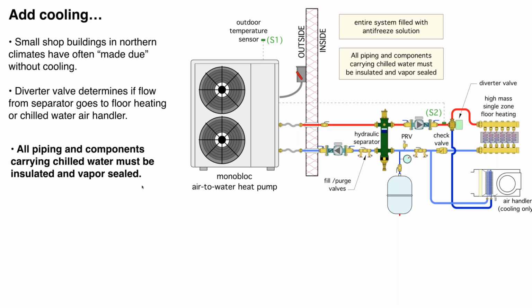So it's a simple modification, and I like this idea because some of these facilities, at least the facilities that I see more or less in rural areas in upstate New York, many of these shop facilities don't have cooling. They just turn on fans, they open the doors and the windows. But if you can bring a heat pump into the picture, you have the potential to bring additional business by simply saying, how would you like to do cooling in this building by adding that air handler? Now, again, I always stress, if you're dealing with chilled water, which you would in this system, all the piping and all the piping components that are conveying chilled water must be insulated and vapor sealed. You cannot do a poor job with that.